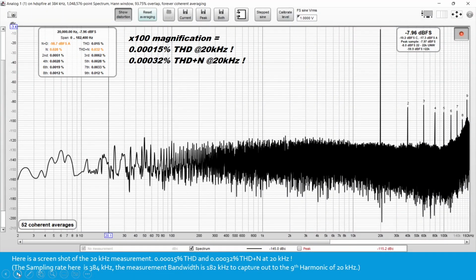Here's a screenshot of the 20 kHz measurement. 0.00015% THD and 0.00032% THD plus N at 20 kHz. The sampling rate here is 384 kHz. The measurement bandwidth is 182 kHz to capture out to the 9th harmonic of 20 kHz. These are some pretty good numbers at 20 kHz.